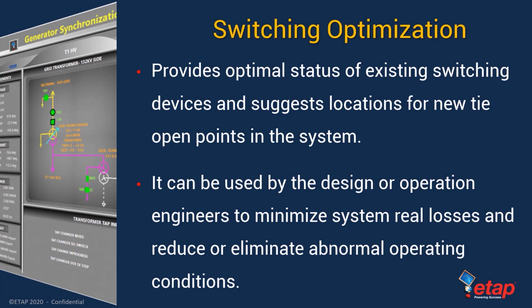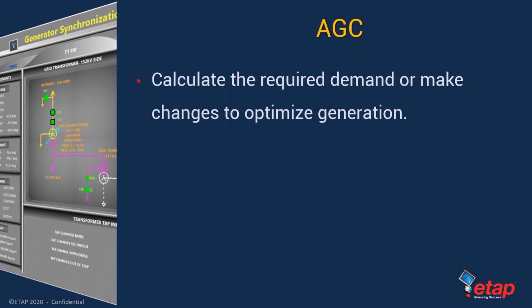Switching optimization. It provides optimal status of existing switching devices and suggests locations for new open points in the system. It can also be used by the design or operating engineer to minimize system real losses and reduce or eliminate abnormal operating conditions. Automatic Generation Control, or AGC, to calculate the required demand or make changes to optimize generation. And it takes into account real-time data, such as frequency and actual generation.